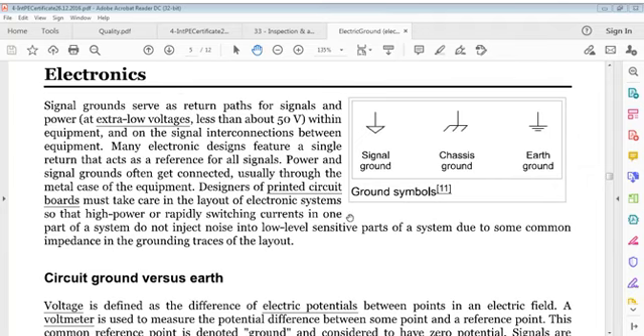Now again I read this. Signal grounds serve as return paths for signals and power at extra low voltages, less than about 50 volts, within equipment and on signal interconnections between equipment. Many electronic designs feature a single return that acts as a reference for all signals. Power and signal grounds often get connected, usually through the metal case of the equipment.